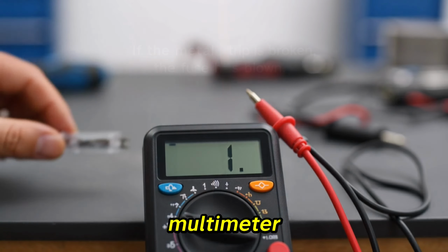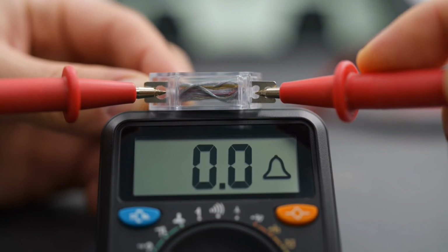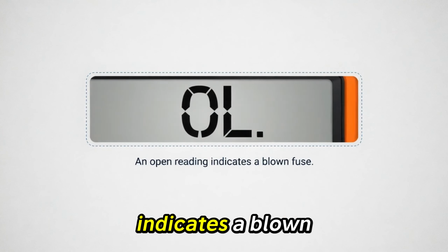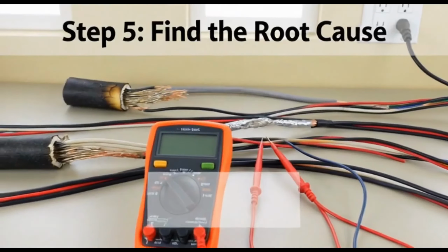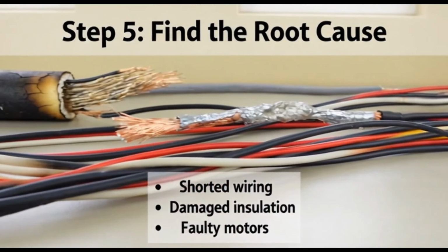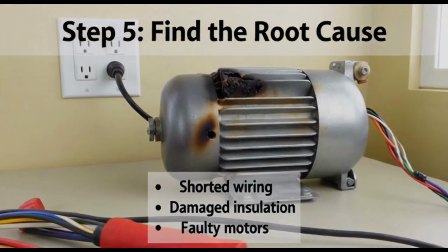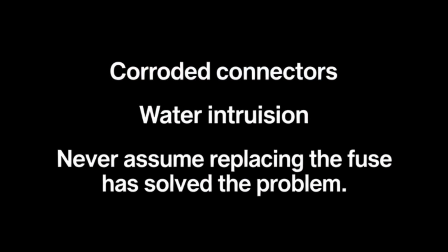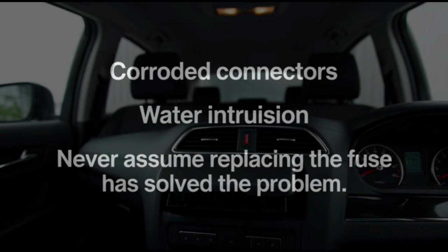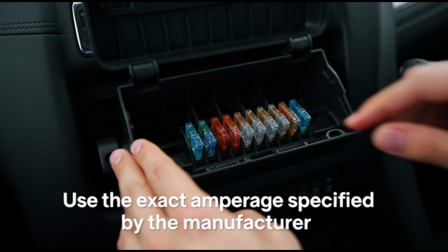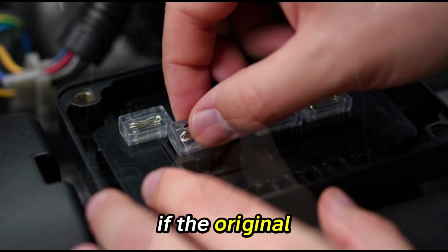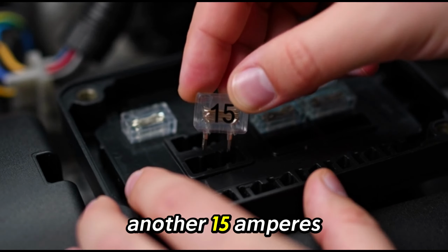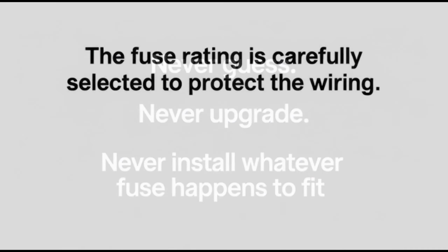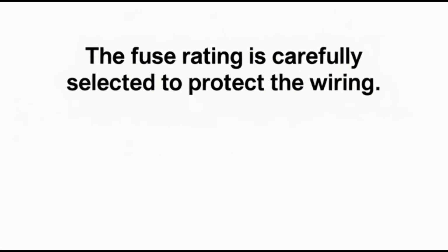Step 4. Test with a multimeter. Use continuity mode. A good fuse should show continuity. An open reading indicates a blown fuse. Step 5. Find the root cause. Investigate shorted wiring, damaged insulation, faulty motors, corroded connectors, and water intrusion. Never assume replacing the fuse has solved the problem. When replacing a fuse, always use the exact amperage specified by the manufacturer. If the original fuse is 15 amperes, replace it with another 15 amperes fuse. Never guess, never upgrade, never install whatever fuse happens to fit. The fuse rating is carefully selected to protect the wiring. Using the correct fuse ensures safe operation and proper circuit protection.